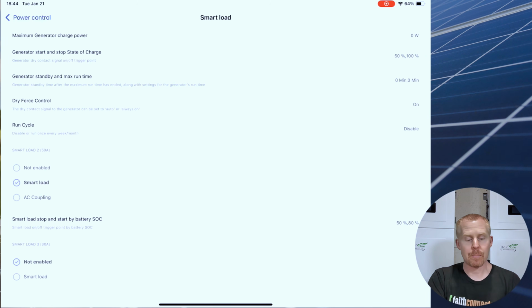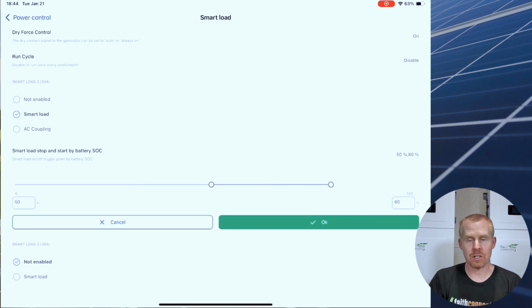So the smart load option on any of these breakers, you can see right here, smart load start and stop by battery state of charge. So when do you want it to start? Which in this case is going to be when your battery state of charge is above 50%, turn it on, and stop it, turn it off once it gets to 80%.